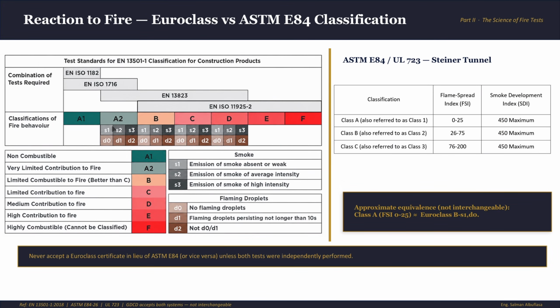What about A2? A2 means very limited contribution to fire. What does that mean? That means the material isn't fully non-combustible, but its contribution to fire development is so small that it behaves similar to A1. In order to claim the A2 category, we need to pass one of these tests, 1182 and 1716, but with less strict requirements or limits. And on top of that, the EN 13823, the single burning item or the SBI test. And now from category B all the way to D, limited combustible to fire, limited contribution to fire, and medium contribution to fire, use the same two tests, the 13823 and 11925. The only difference is how much they're allowed to contribute to fire growth, with B being the most strict among them.